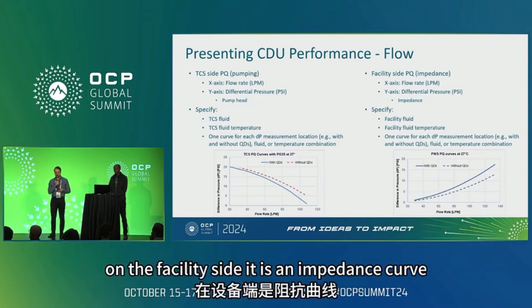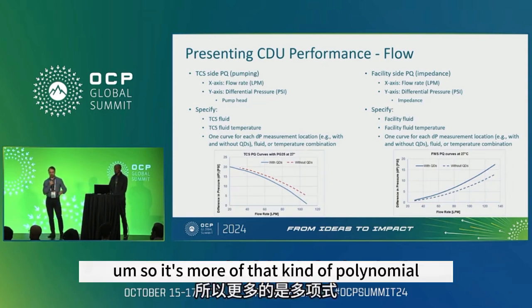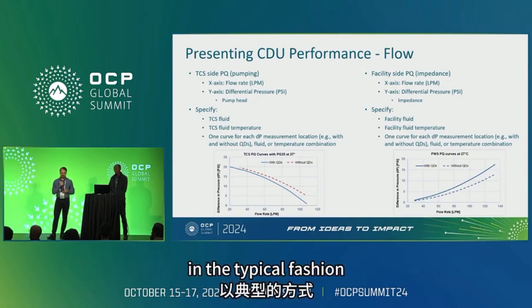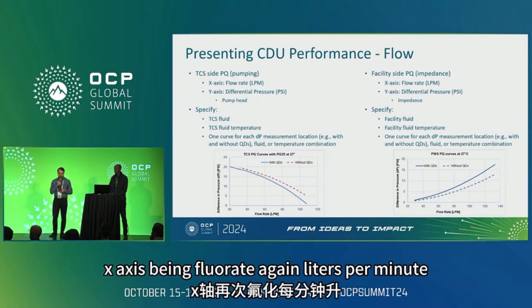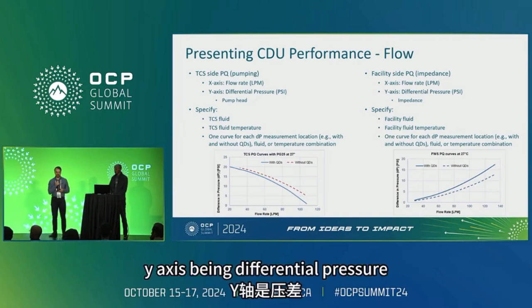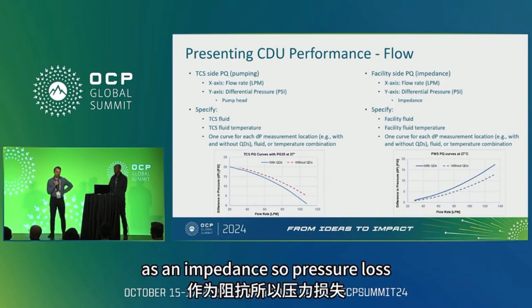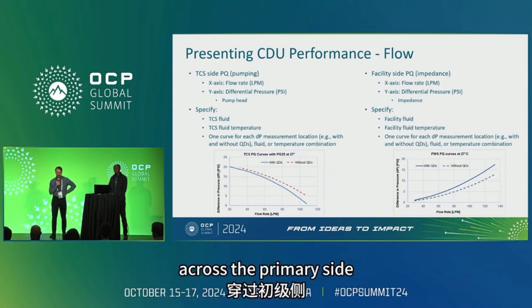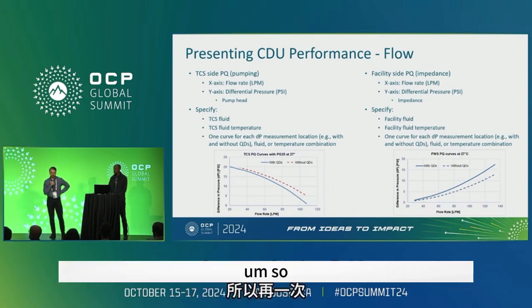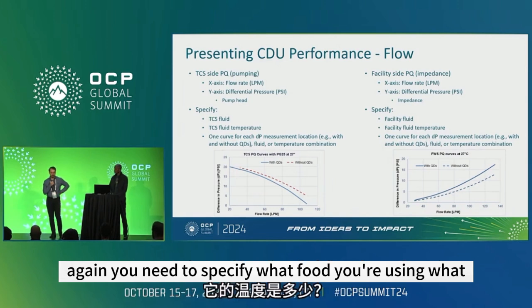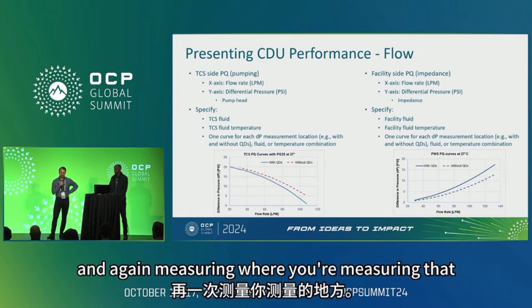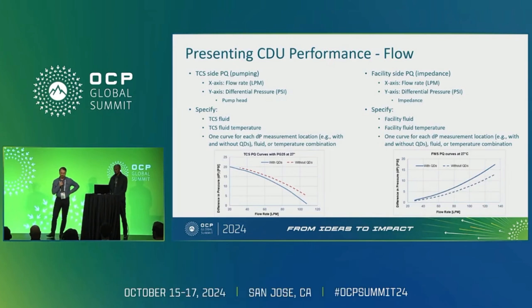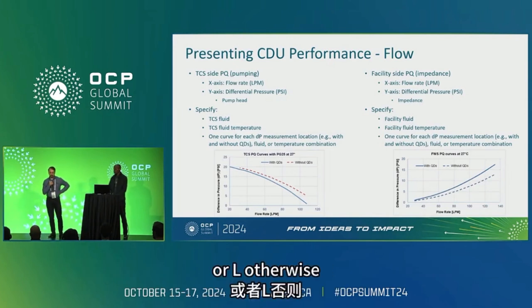On the facility side, it is an impedance curve, so it's more of that kind of polynomial in the typical fashion. X-axis being flow rate again, liters per minute, y-axis being differential pressure as an impedance, so a pressure loss across the primary side. Again, you need to specify what fluid you're using, what temperature it's at, and again, measuring where you're measuring that with QDs, without, or otherwise.